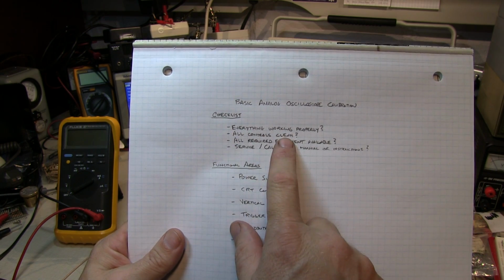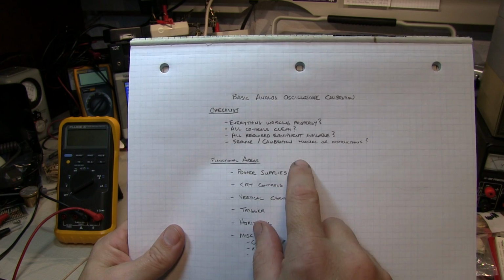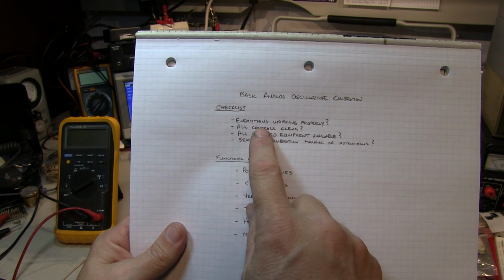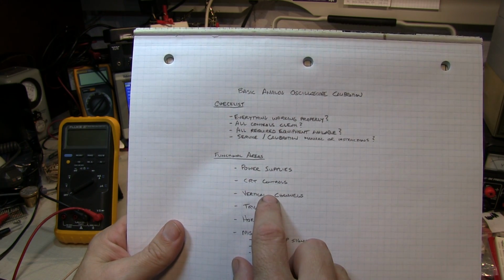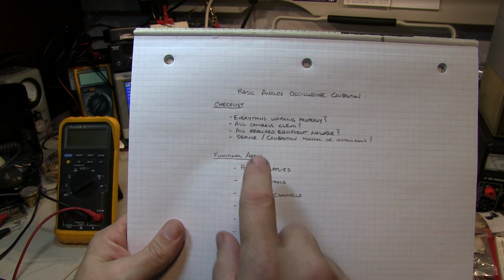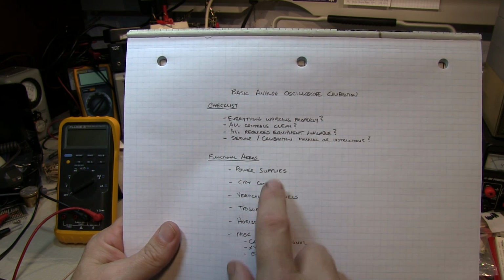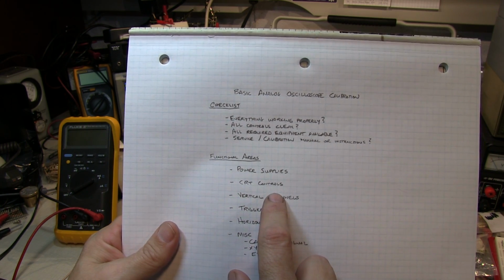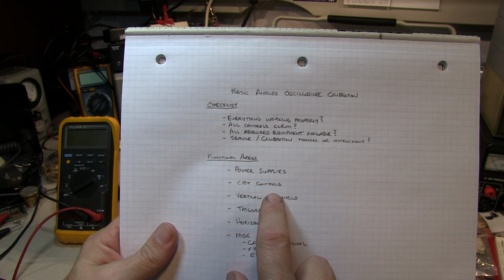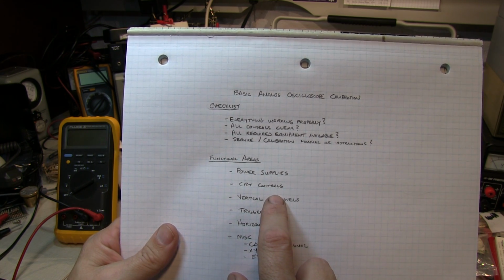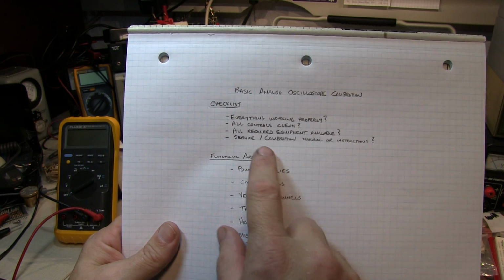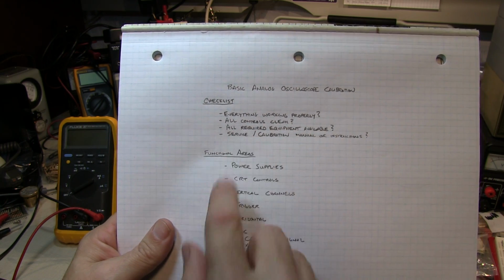And are all the controls clean? When you adjust the pots and the switches, if they're dirty, you really need to clean those first before you begin your calibration. And do you have all the equipment required to do the calibration? That might mean a high voltage probe. It may mean some calibrated signal sources and things like that.